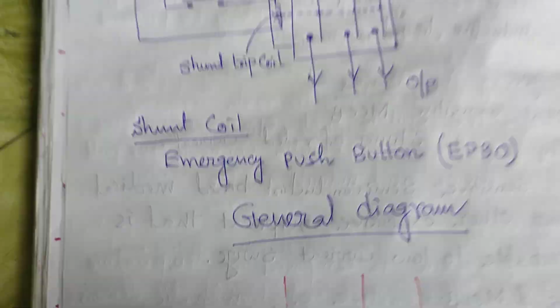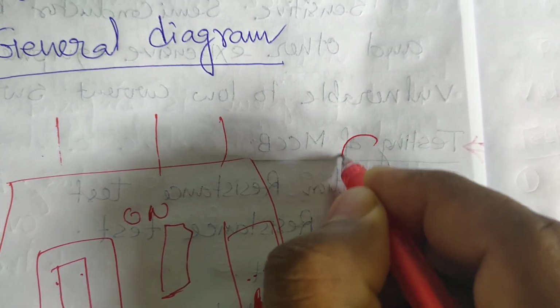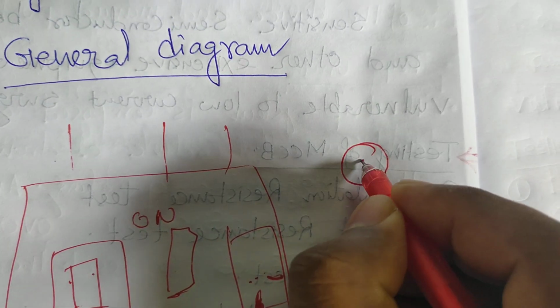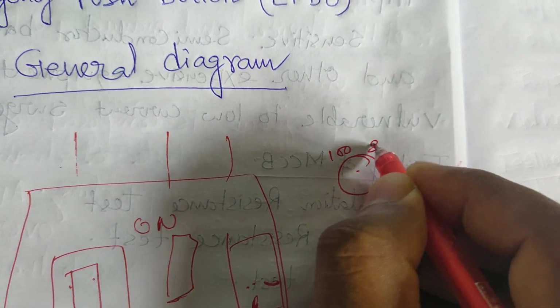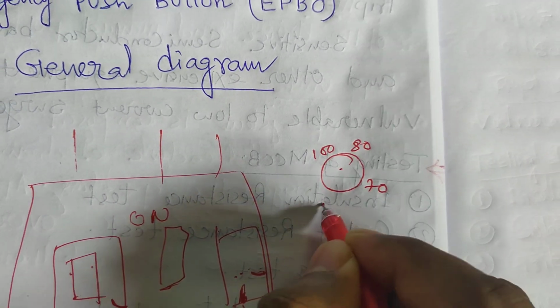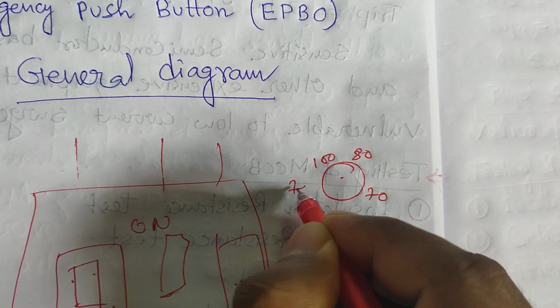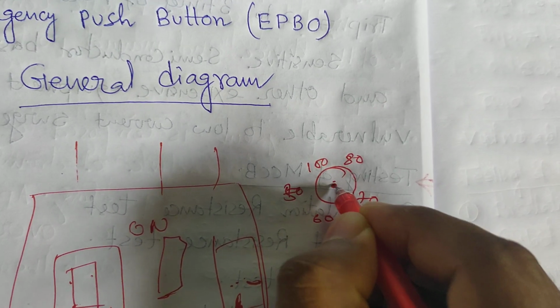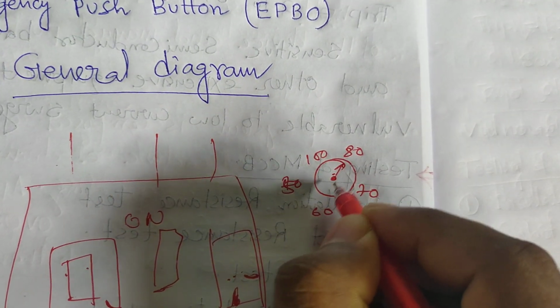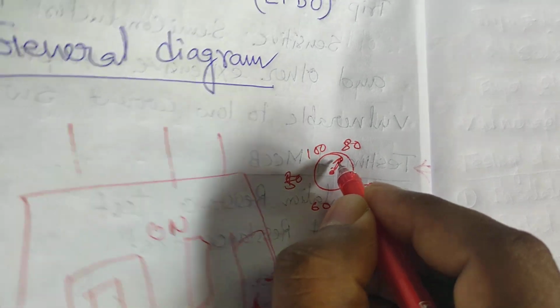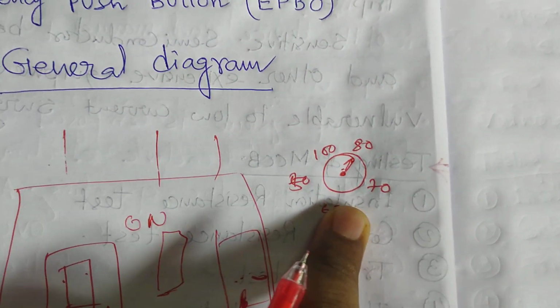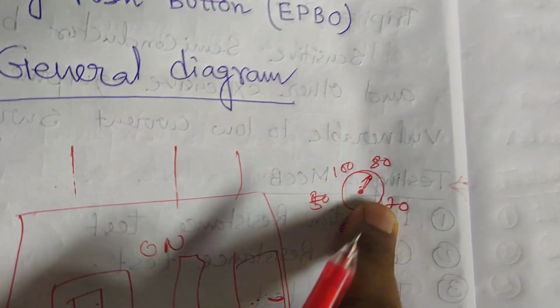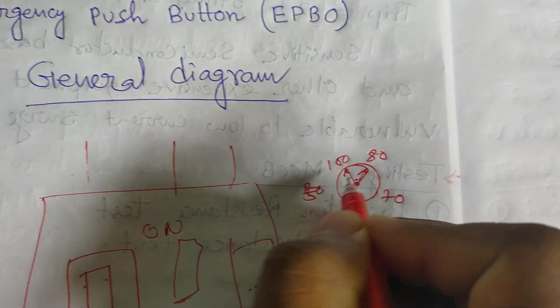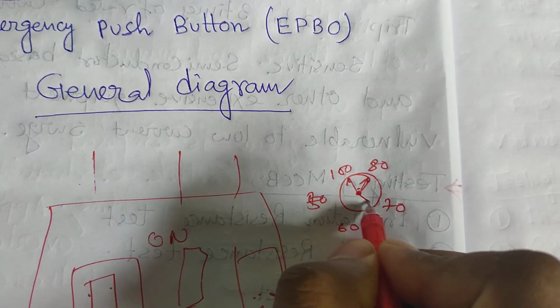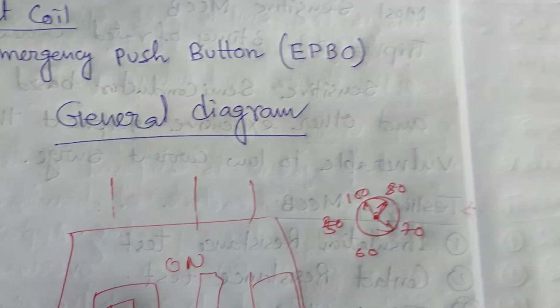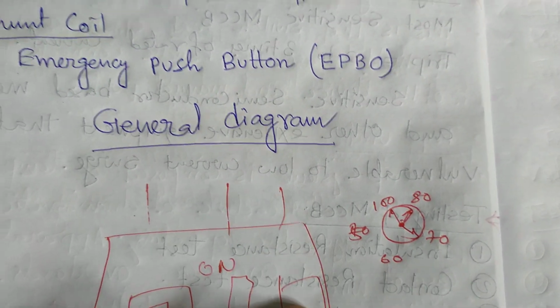The trip setting means a round type notch will be there, with markings 100, 80, 70, 60, 50, and one notch. If you set it at 80%, it will be treated so that when 80% current flows, it will trip. With 100% current flowing, then trip. If 70% current flows, then trip. So this is the trip setting.